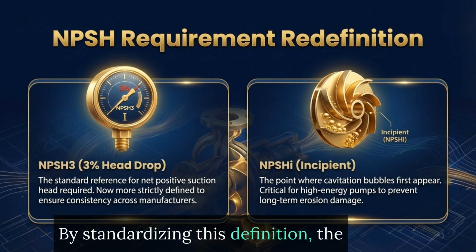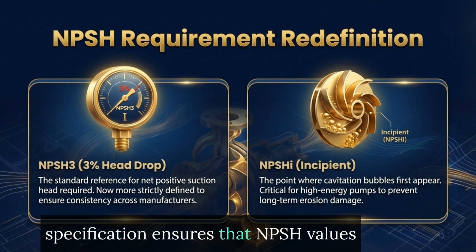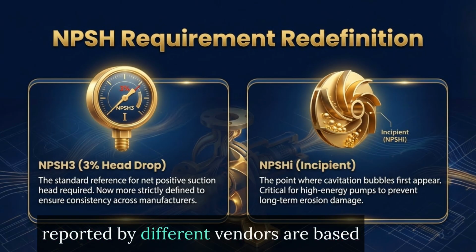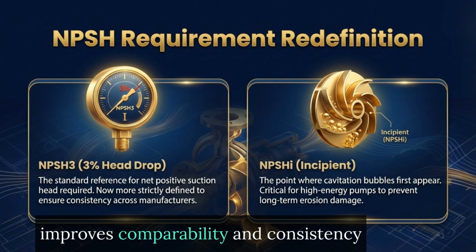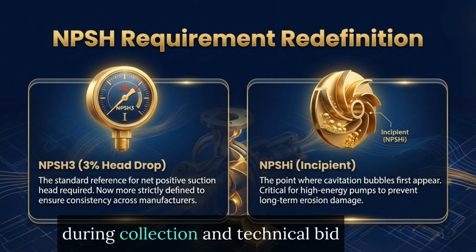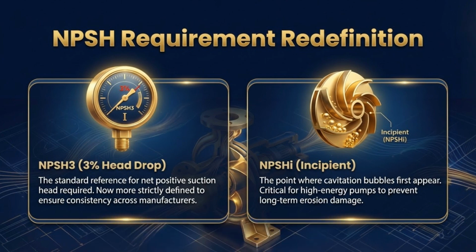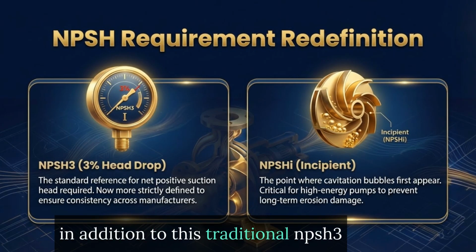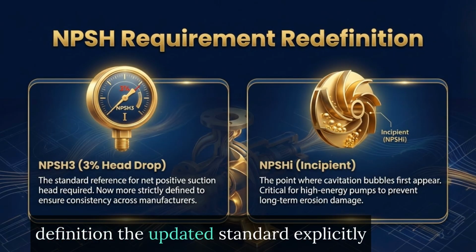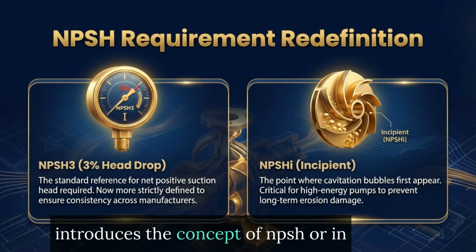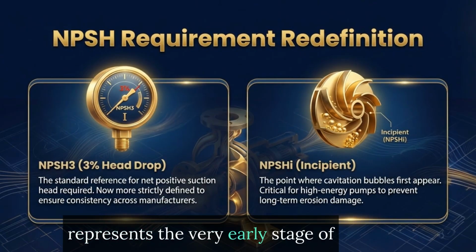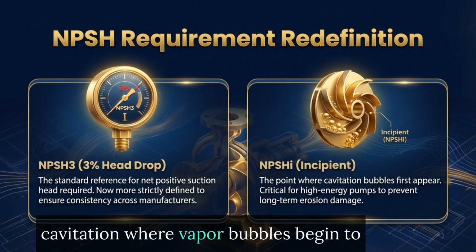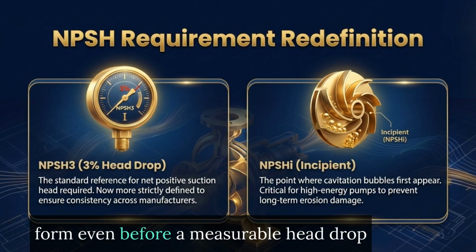By standardizing this definition, the specification ensures that NPSH values reported by different vendors are based on the same performance criteria, which improves comparability and consistency during pump selection and technical bid evaluation. In addition to this traditional NPSH3 definition, the updated standard explicitly introduces the concept of NPSHI, or incipient net positive suction head.